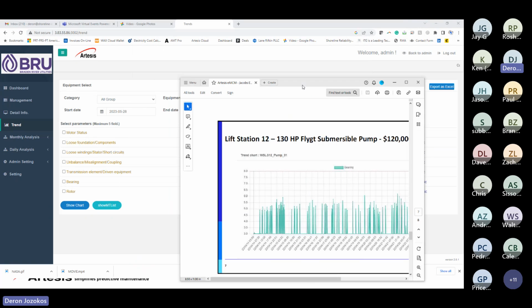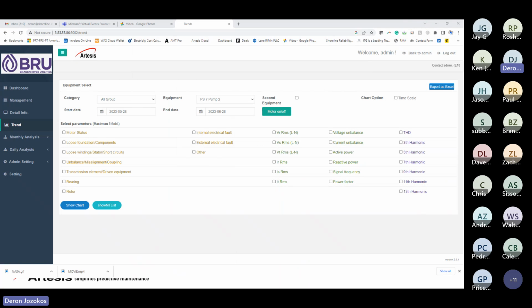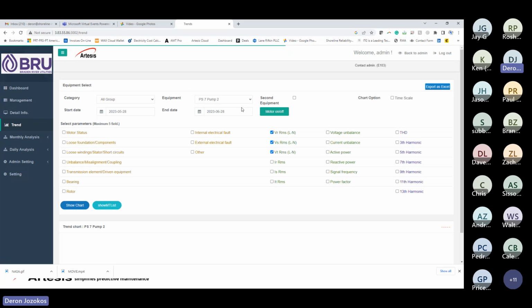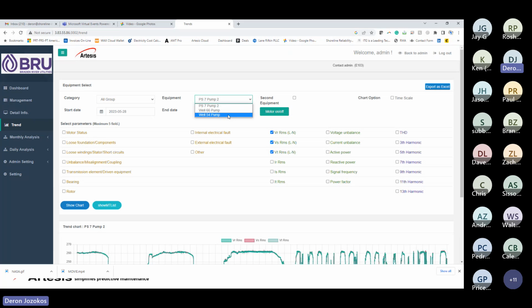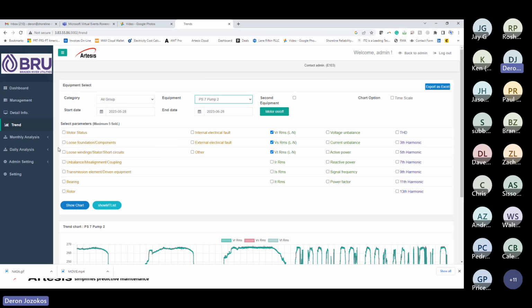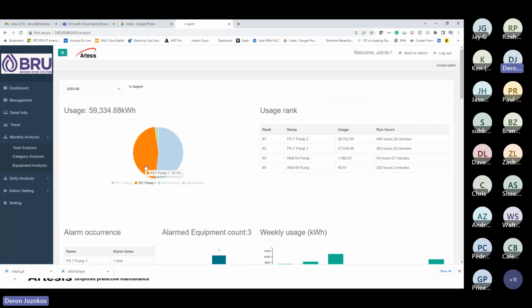And let me pull this out of here. Okay, so that's a good example of the use of your trending page. You can compare, say, one machine to another, pump one, pump two, compare the data from one machine to another. And then the last two tabs on the online systems, monthly analysis, daily analysis of your total assets. It can break it out into all the different categories and show you what's using the most, in this simple pie chart here. You can look at it each month. You can break it into categories and specifically down to the equipment level.